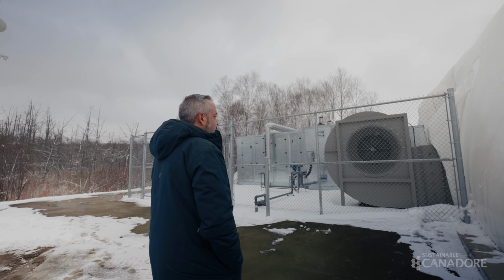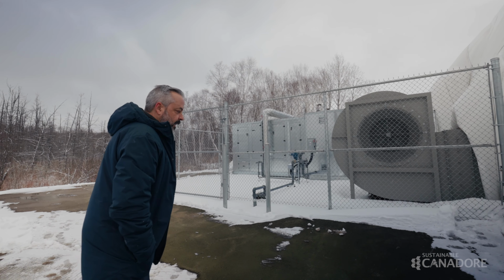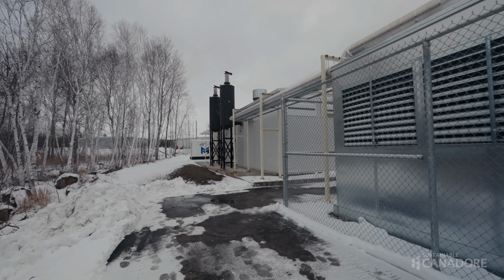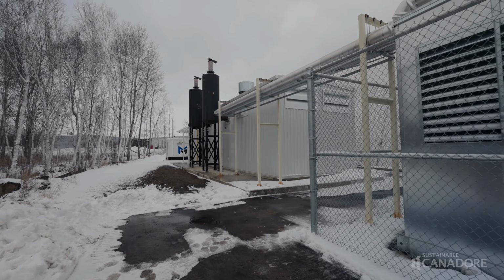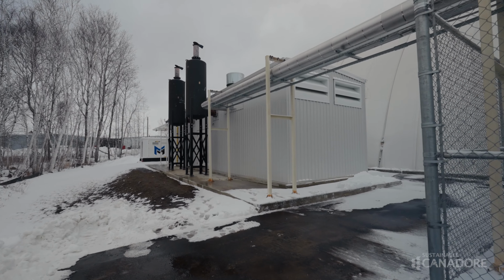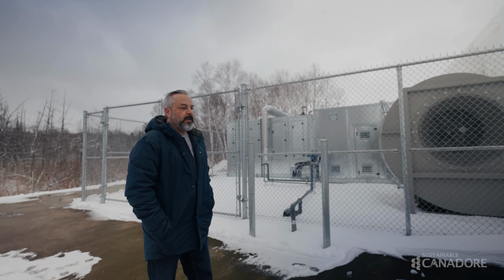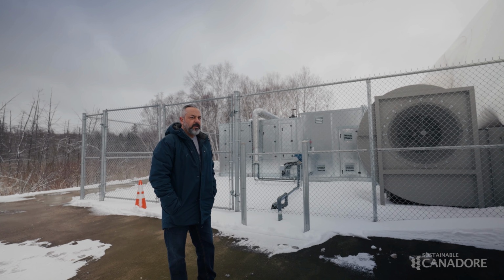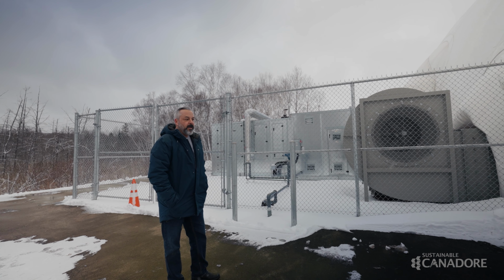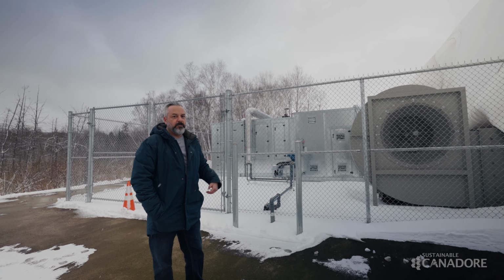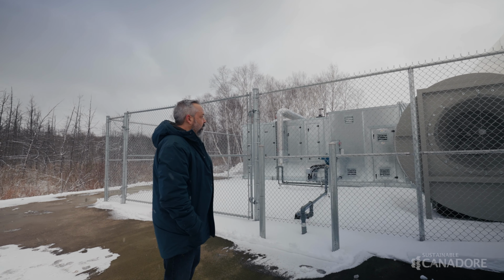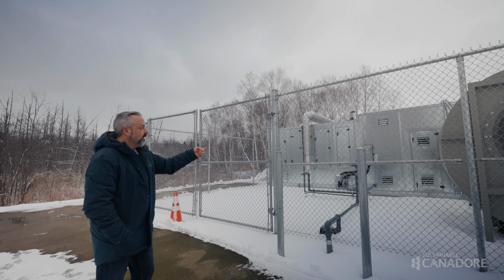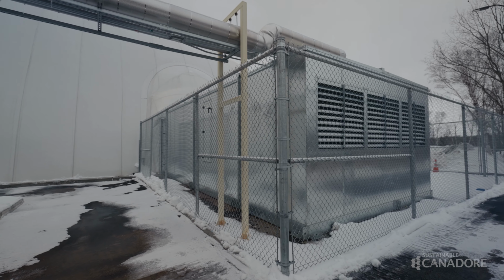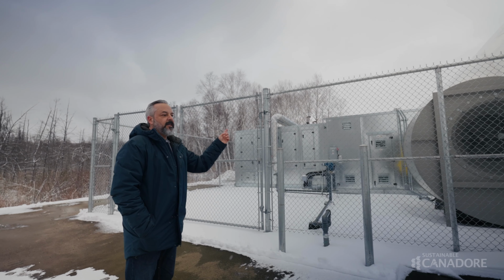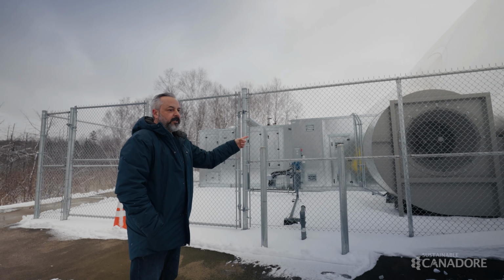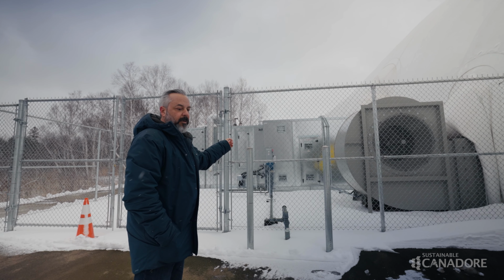As I walk, you can see that at the back of the dome we have our heating, ventilation, and pressure control system. The 85,000 square foot dome we erected is supported through air and air pressure. We must maintain air pressure, or the dome will deflate and collapse. Here we have our heating and ventilation, which not only feeds air into the dome but provides heating for it, plus a backup auxiliary fan in case the main system fails.